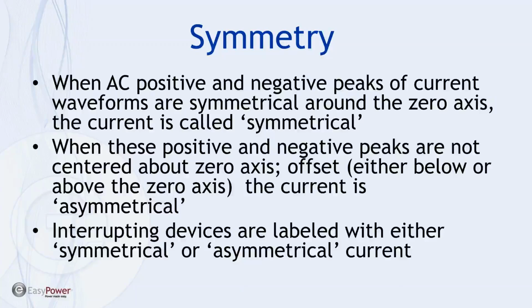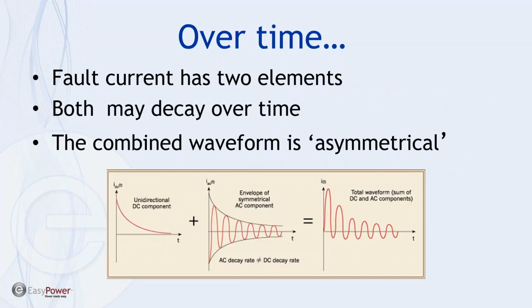operate properly. Now, over time, and when we say over time, we're talking about a number of cycles, the fault current has two elements, and both may decay over time based upon the changes in the system during the fault. When we look at the fault being generated, or the fault as affecting the utility supply or the power supply of an AC system, it looks something like the waveform here in the center, where even though it diminishes because of changes in the system, it still is symmetric in that it's balanced around the zero axis.